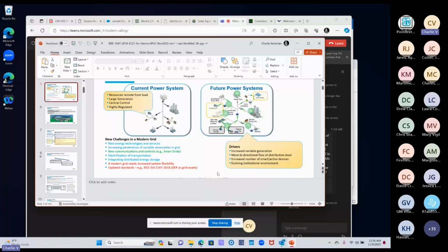But the degree of loss of inertia at this point, the ability to coordinate all the way down to, let's say, the feeder fuse, due to the impact of a DER up through a recloser to an upstream breaker across a transformer - that traditional time over current regime is still working.